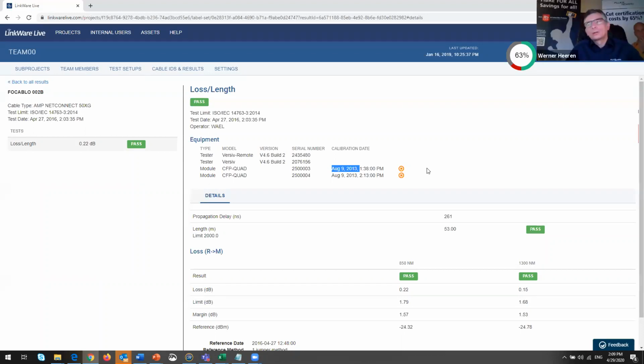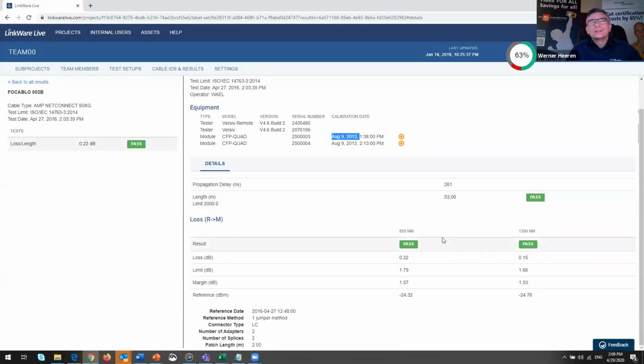Yeah. So I think the underlying question was, you still get a pass. The test is passing, yes, but the calibration is not within the yearly calibration interval. It's not giving a fail. Yeah, and you could be lucky if you get a pass. Like here, and we know our demo units are not heavily used on sites, but you might have problems with machines; if you have a problem in the machine, you might get a failing pass.